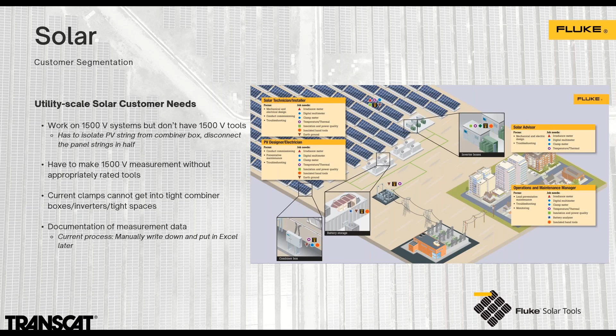With these applications, there's a lot of commissioning involving wire management setup, environmental concerns, and safety hazards, plus confirming everything was wired correctly, insulation tests were done, and grounding was accomplished for safety. Then operations and maintenance comes into effect, with a lot of documentation maintained so these systems can be commissioned and finally put onto the grid for use.